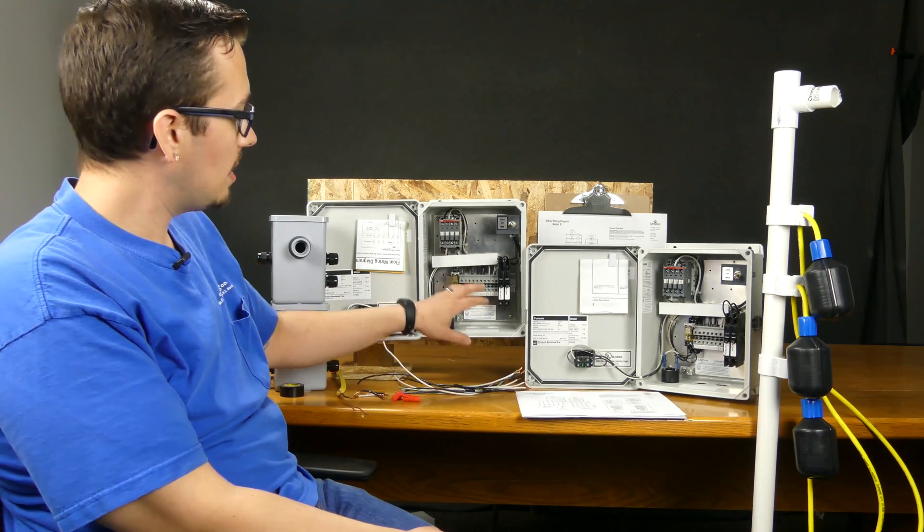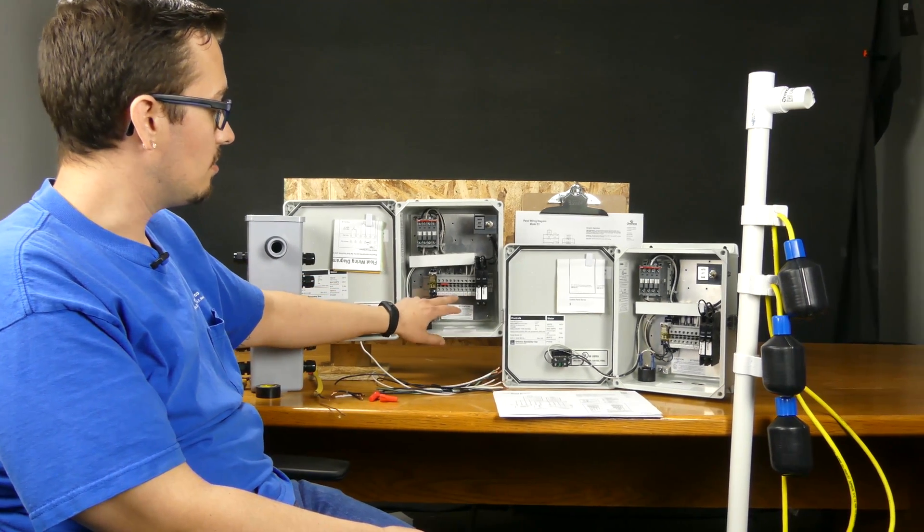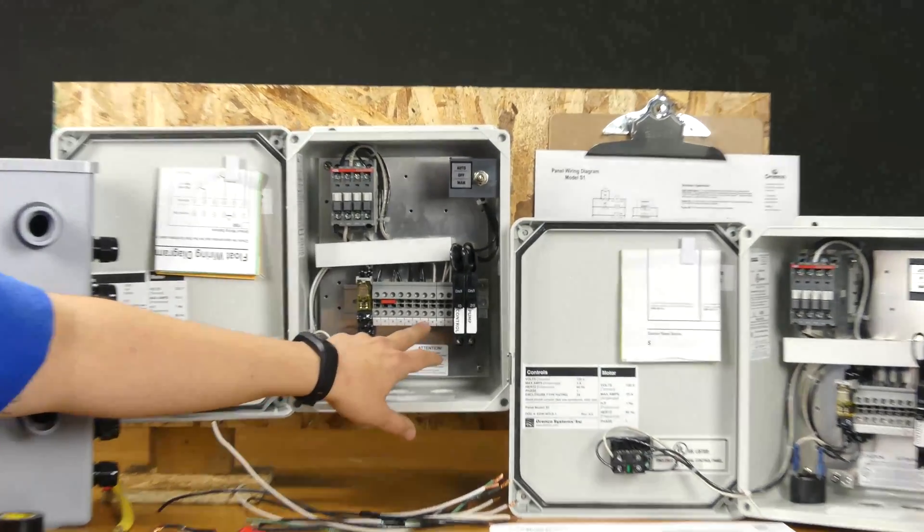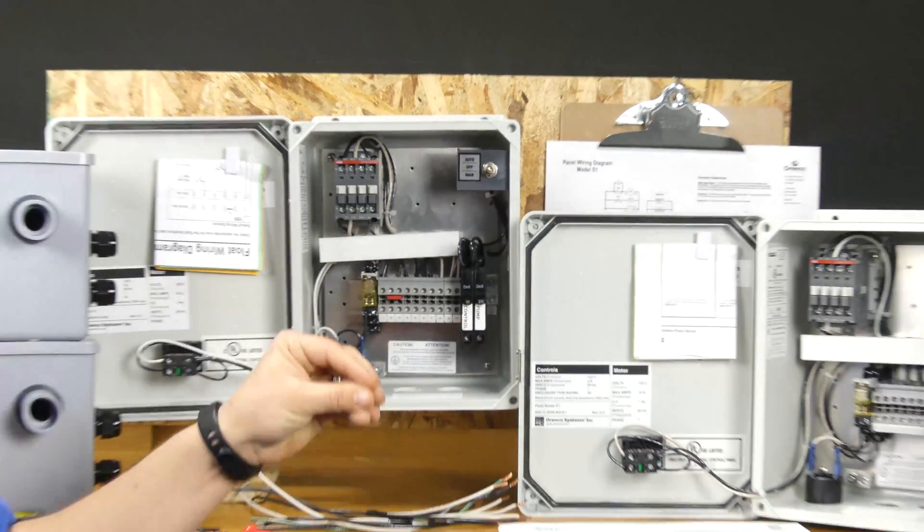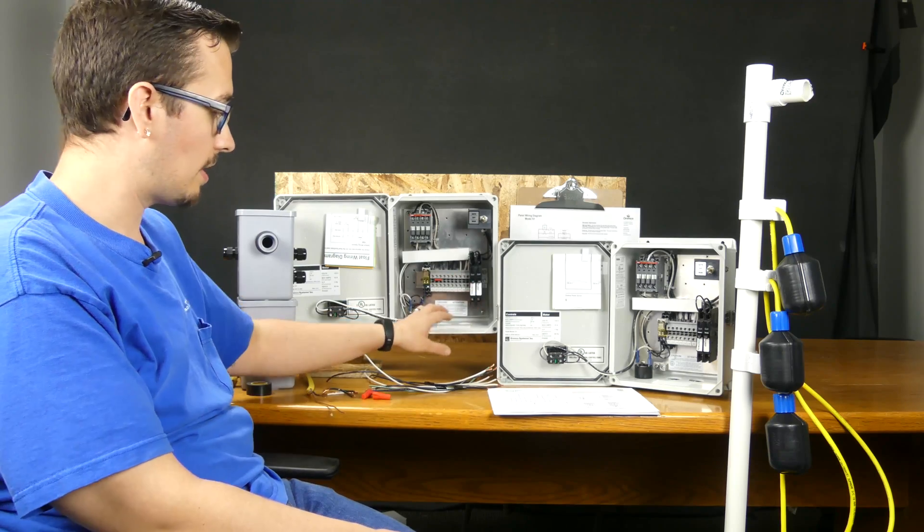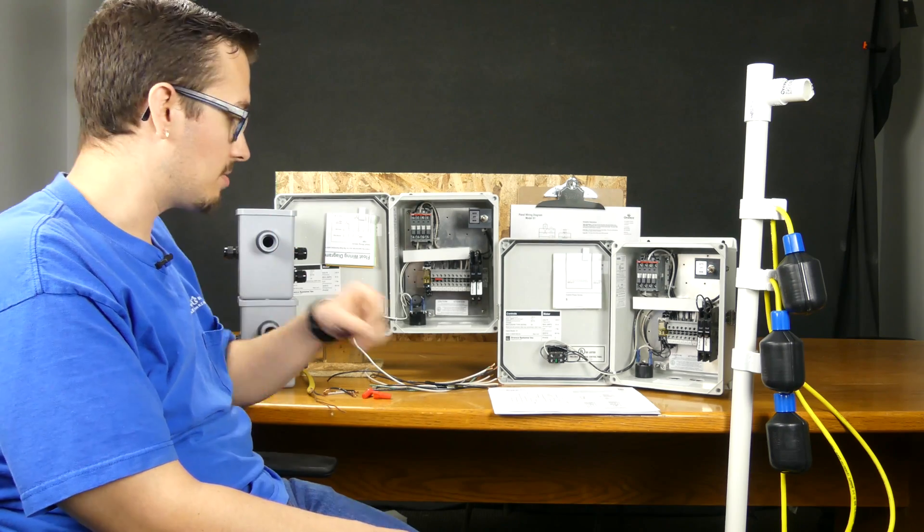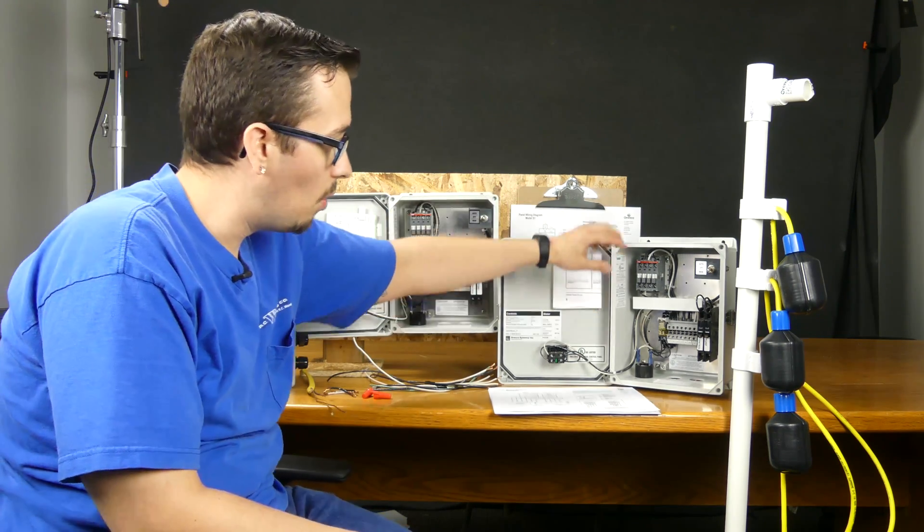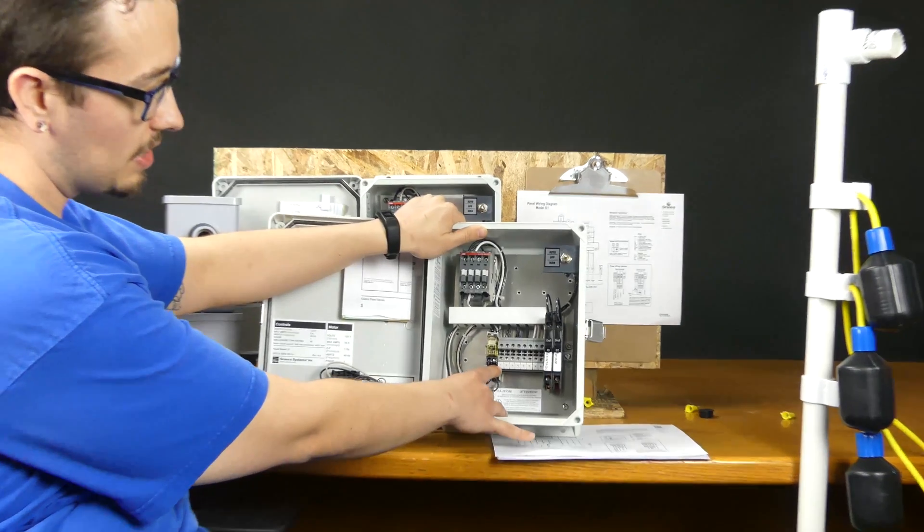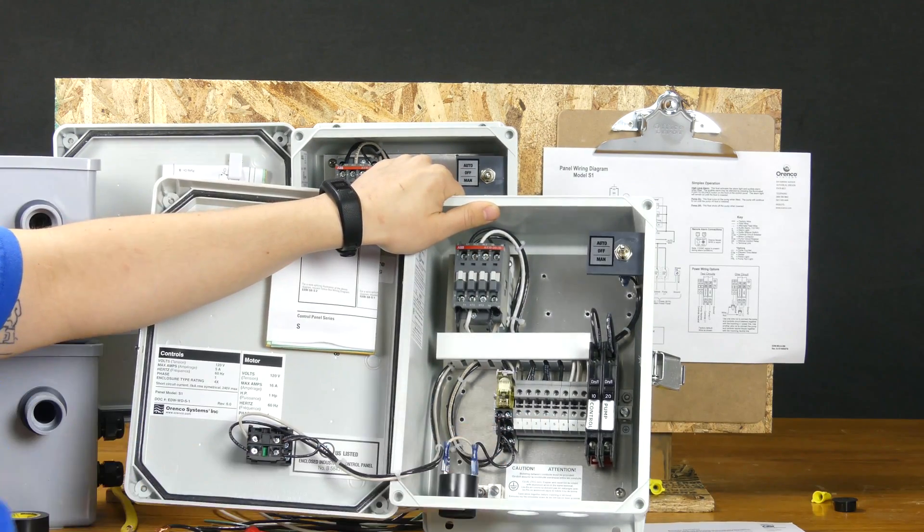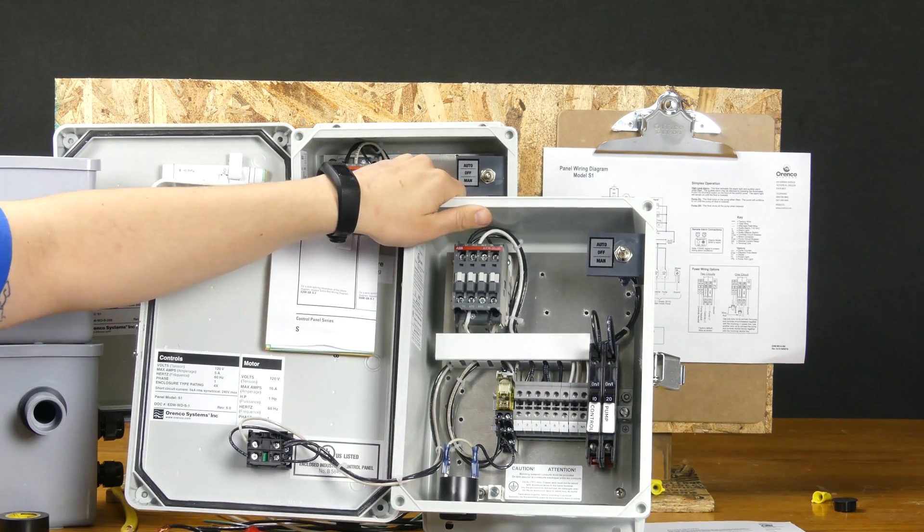Briefly to summarize, the biggest difference is now in the new panel you're landing all six of your float wires, as opposed to before you had to create a common in the splice box, or with the way that we did it, we would create a common inside of the panel down here. With the old panel, you've only got five spots for your floats, and that's where that common came into play to pair that number of floats down.